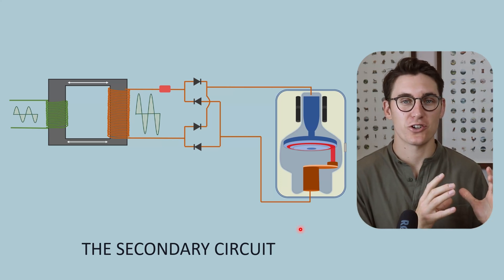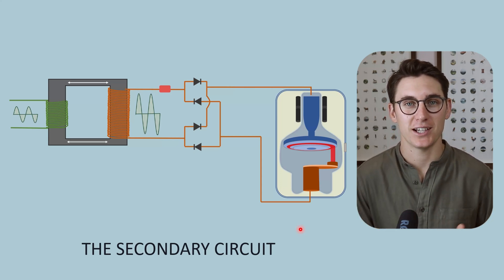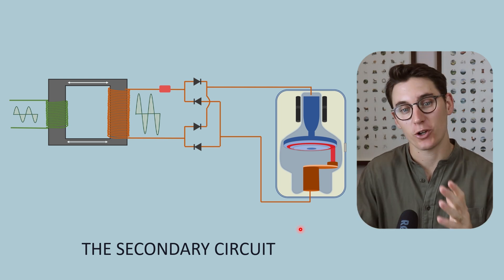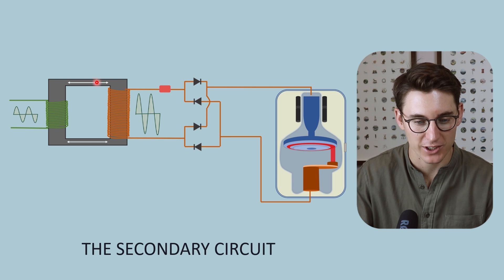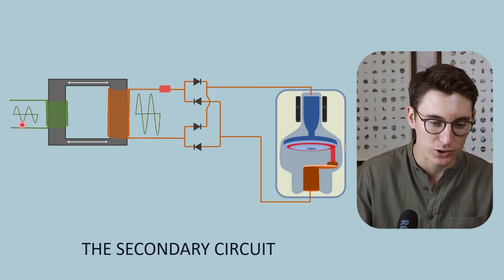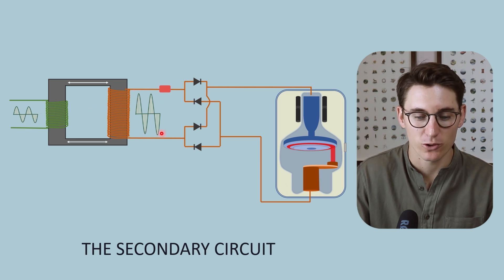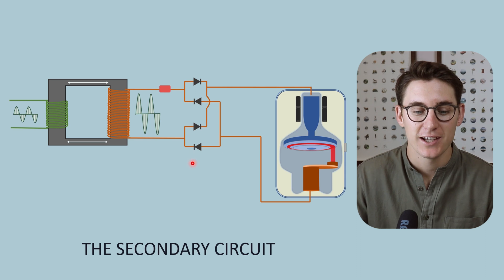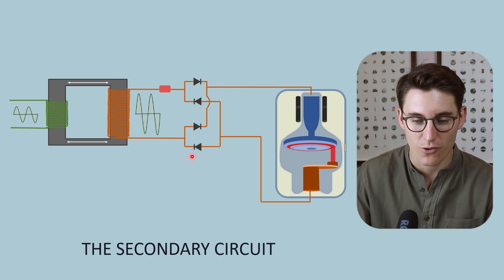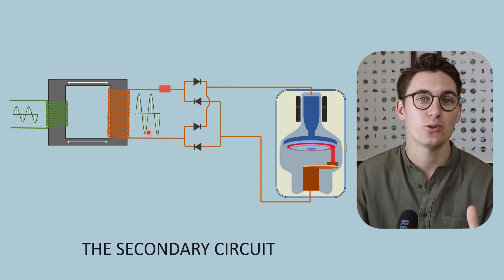We've seen how our primary circuit allows us to select our kVp and determine our exposure time. We've also seen how, in combination with the secondary circuit through the process of step-up transformation, we've taken a low voltage alternating current and transformed it into a high voltage alternating current. Now let's look at the secondary circuit and how it uses the process of rectification to change this alternating current into direct current.